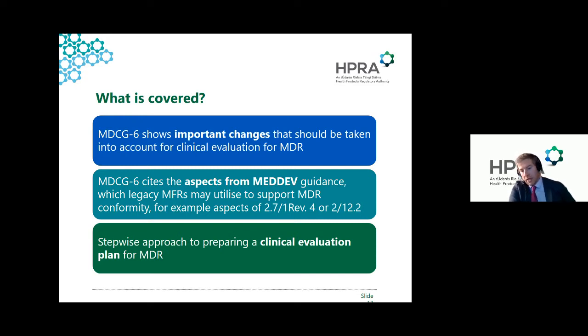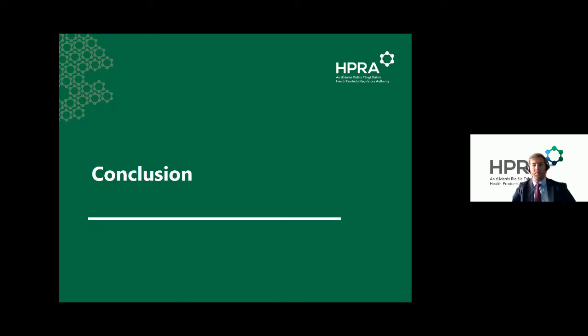An important aspect of MDCG 2020-6 — the sufficient clinical data guide — is that it helps show which parts from current directive guidance are still applicable and can still be used. In an annex to the document you'll see the parts of the MEDDEV that remain applicable. It also harmonizes with the stepwise approach in MEDDEV 2.7/1 revision 4 — the stepwise methodology for creating your clinical evaluation covering identification, appraisal, analysis, etc. — written to harmonize with the current methodology.